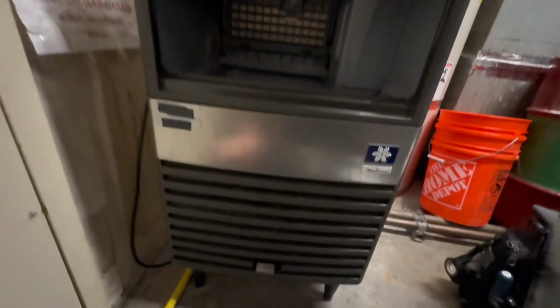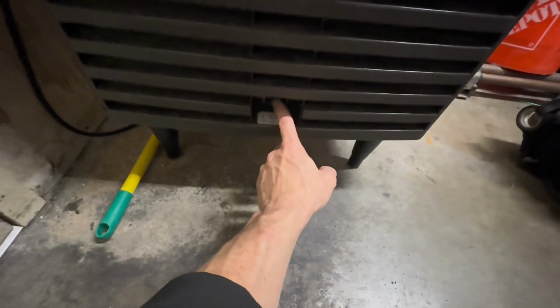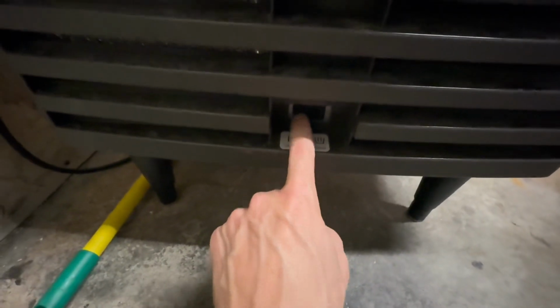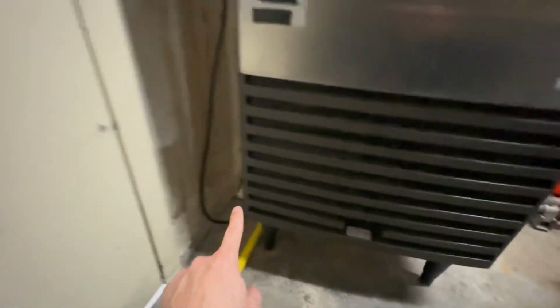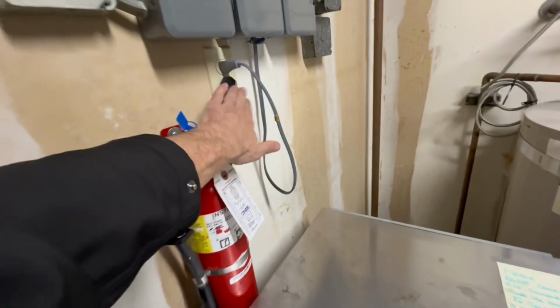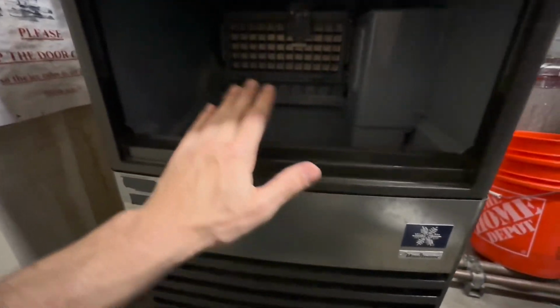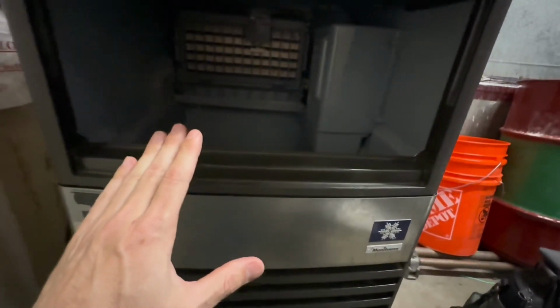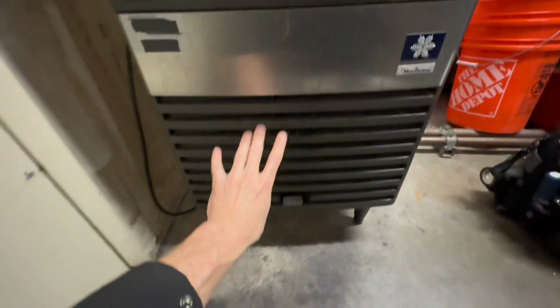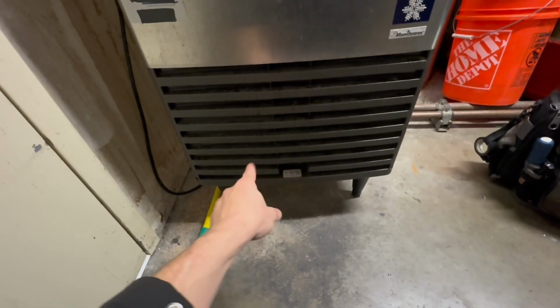Today we're doing a service call on a Manitowoc QM45A. Looking at the machine, I'm looking at my power switch down here. It's switched to the on position and the machine is plugged in, but I'm not seeing any ice. I'm gonna take this front panel off, look at my control board, see if I even have any lights on.